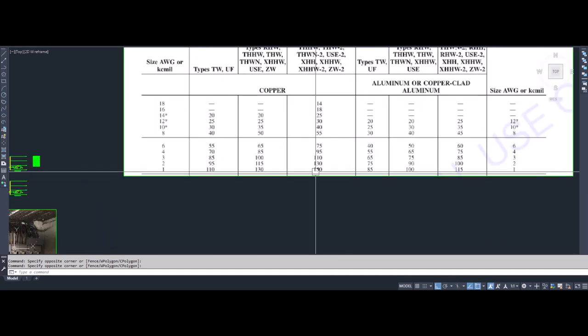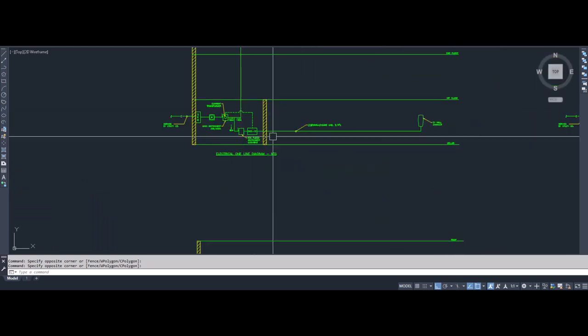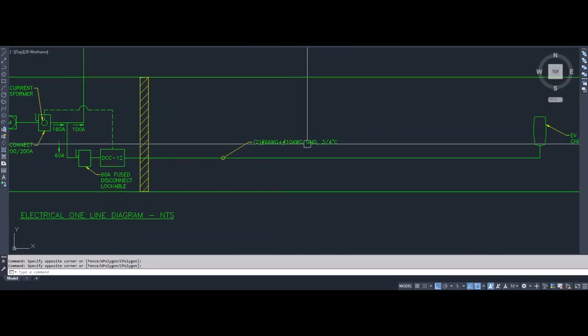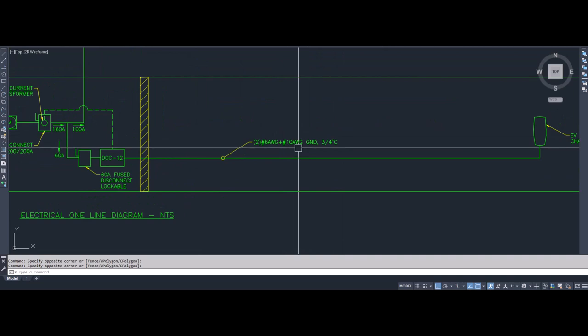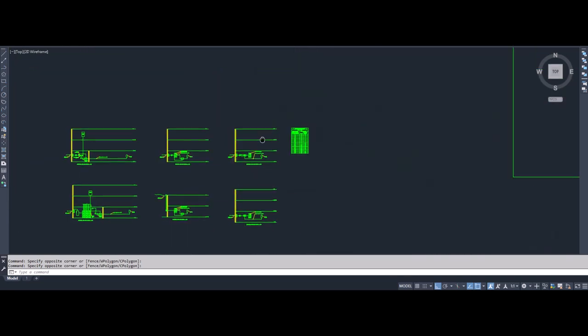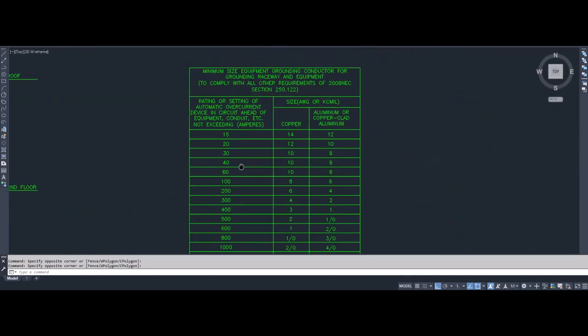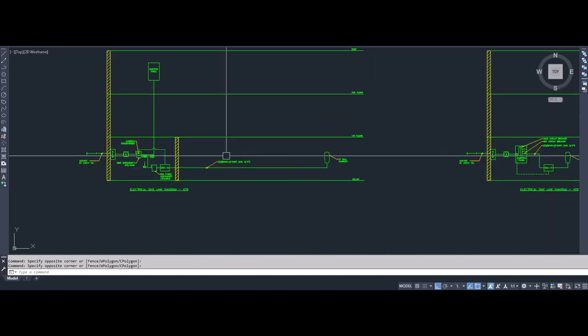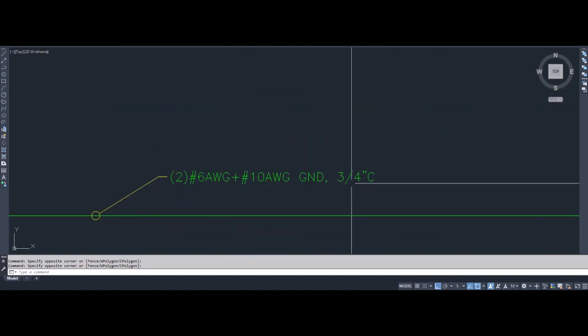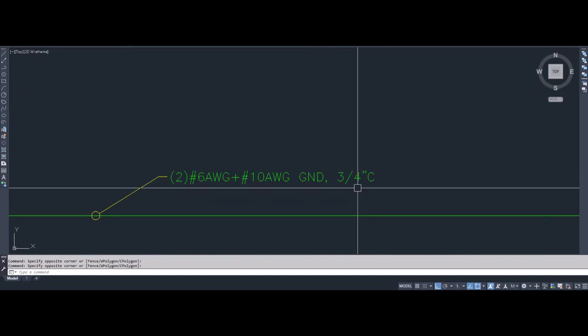As you can tell in this column, the amperage is going up. So you have a 6 in that case, and a number 10 ground. To size the ground, you use this table here, where if it's a 60 amp breaker and you want to use copper, which is generally better to use, you need a number 10 AWG size wire ground. So that's how you size the ground, and you have to size the conduit next.